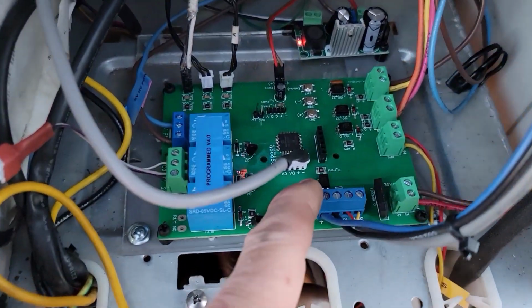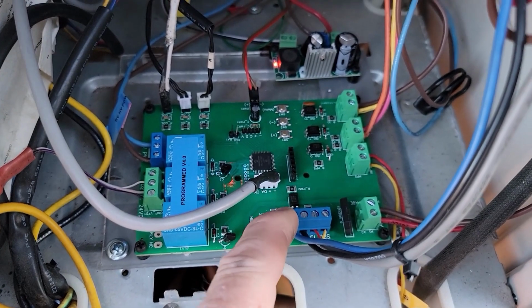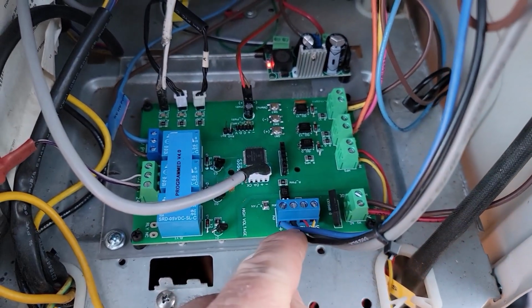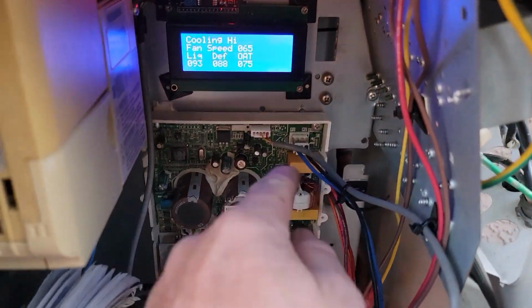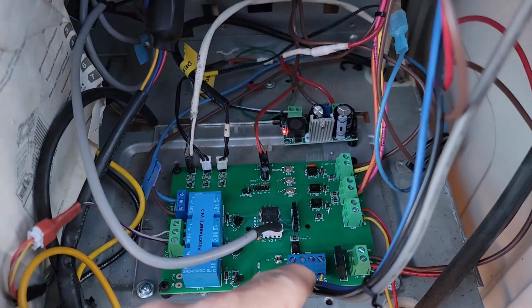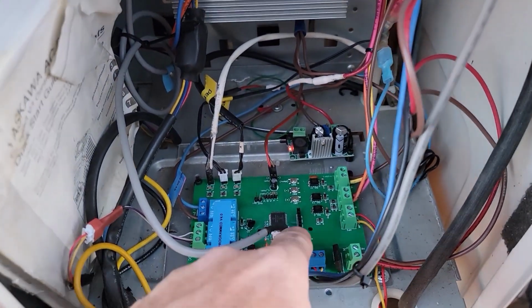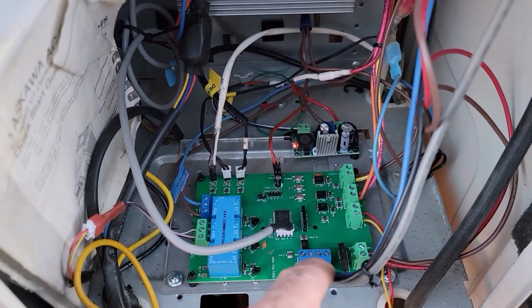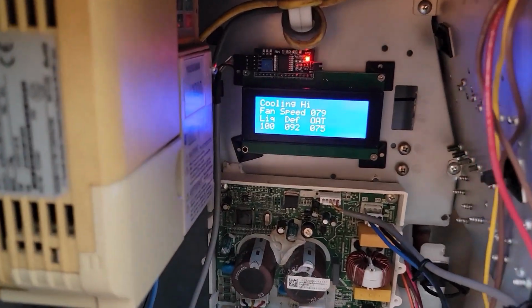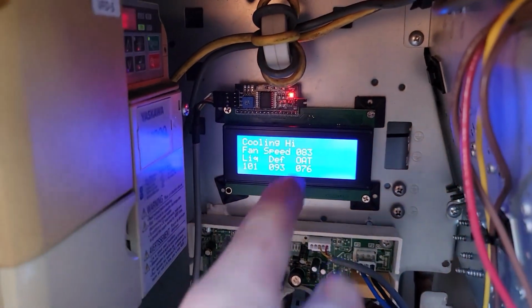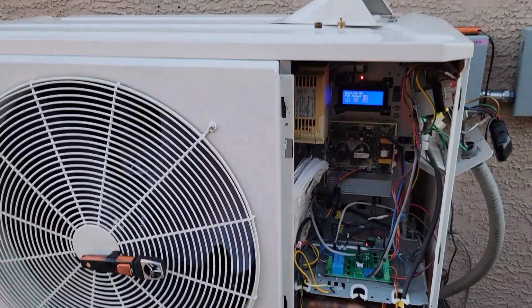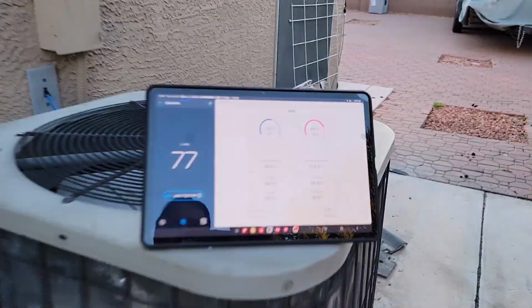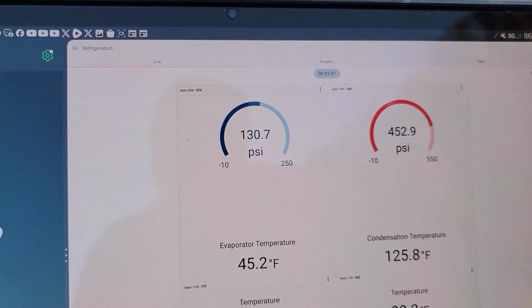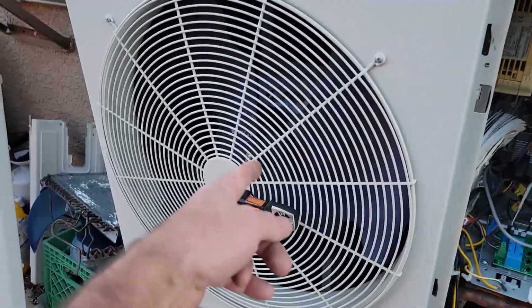It's pulsing this optical isolator filter, goes through this. I got to be careful. This is high voltage DC on this side coming from the IPM, and then you just have the 15 volt supply to this circuit I made right here, and then the voltage going back to run it. So liquid line's getting warm enough that the fan speed algorithm's kicking up, so these should start rocking here once that pulse width modulation gets high enough. And you see it's jumping way up on the pressure, 450, and there they go.